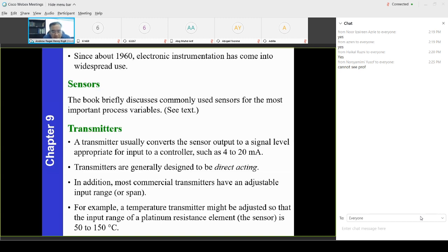If you measure the temperature of boiling water, you know it could reach a maximum of 100 degrees Celsius. So you need an instrument that can measure from 0 up to maybe 110, because the limit is around 100 degrees Celsius. For example, a temperature transmitter might be adjusted so that the input range of a platinum resistance element, the sensor, is between 50 to 150 degrees Celsius.